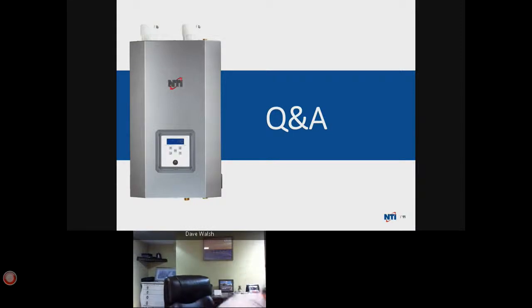Hey, Jason, it's Corey. Can you comment on the combi operation with regards to that added volume compared to some of the other combis on the market, and how that would operate? Right. First of all, with that volume, it presents a challenge because if the volume is ice cold or room temperature, it would typically take longer to receive hot water at the fixtures. So we're utilizing a preheat function that works to maintain some minimum temperature periodically within that volume. What it in effect does is provide better response at the fixtures. But once you get running, as the flow rate and the load change dynamically as the faucets open and close, the mass actually helps to stabilize the temperature delivery.